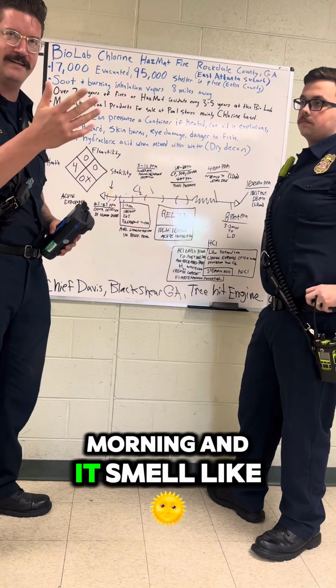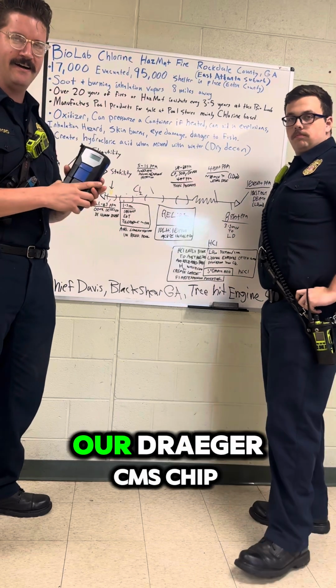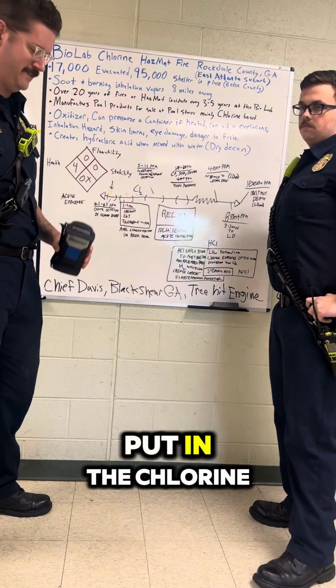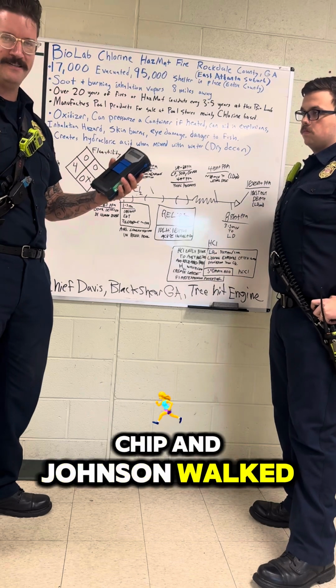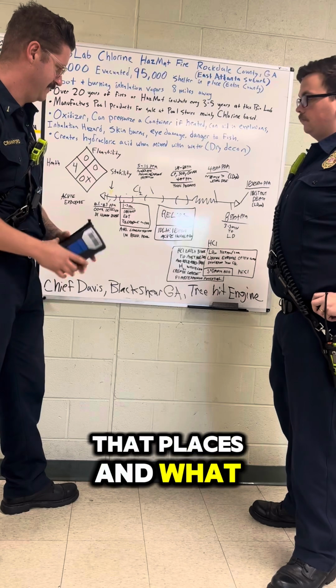We pulled up this morning. It did smell like chlorine in the parking lot. So we popped out our Drager CMS chip monitor, put in the chlorine chip, and Johnson walked around and scanned it. Go ahead and tell them your findings and kind of where that places us and what that means.